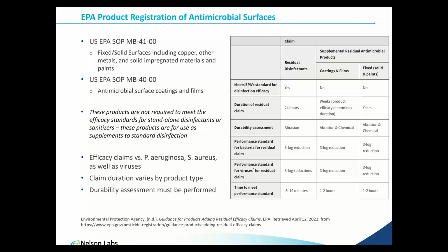The methods include an efficacy assessment of the solid surface materials or coated coupons following repeated exposure to specified chemical solutions with standardized repetitive mechanical abrasions using an abrasion instrument. The chemical solutions are representative of various disinfectants that the surfaces will come into contact with during normal disinfection procedures. So for example, bleach, peracetic acid and hydrogen peroxide, or quaternary ammonium products.